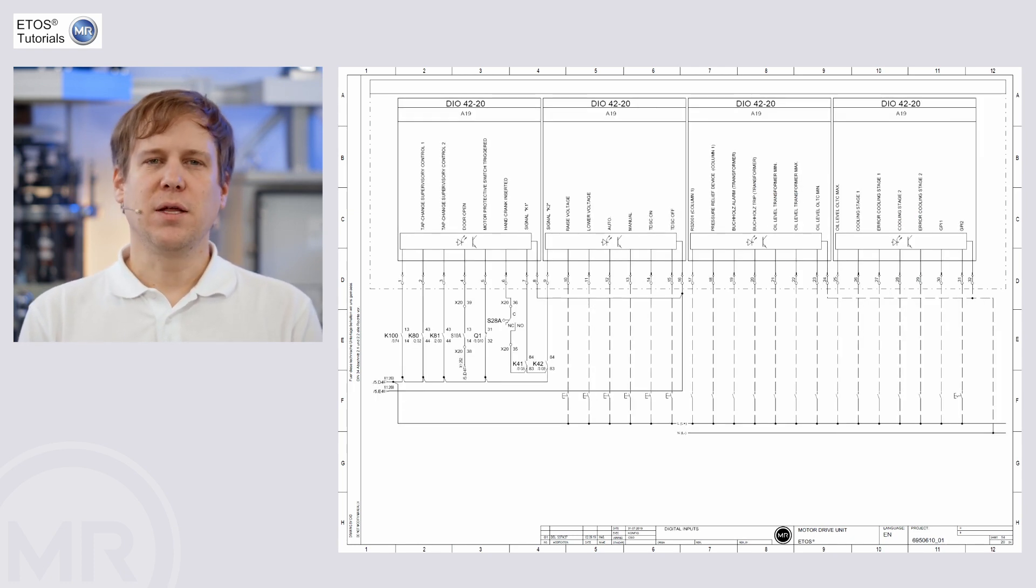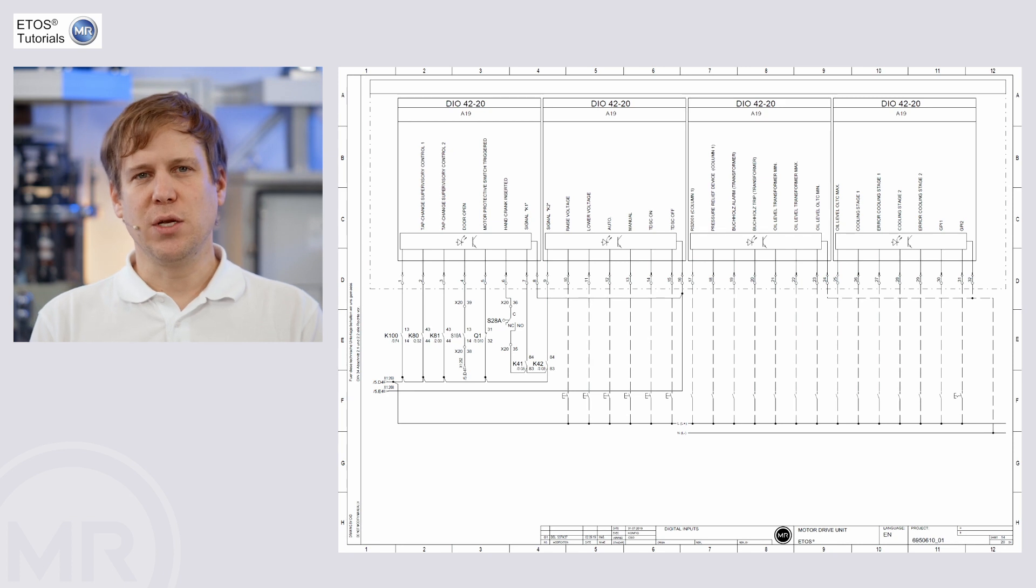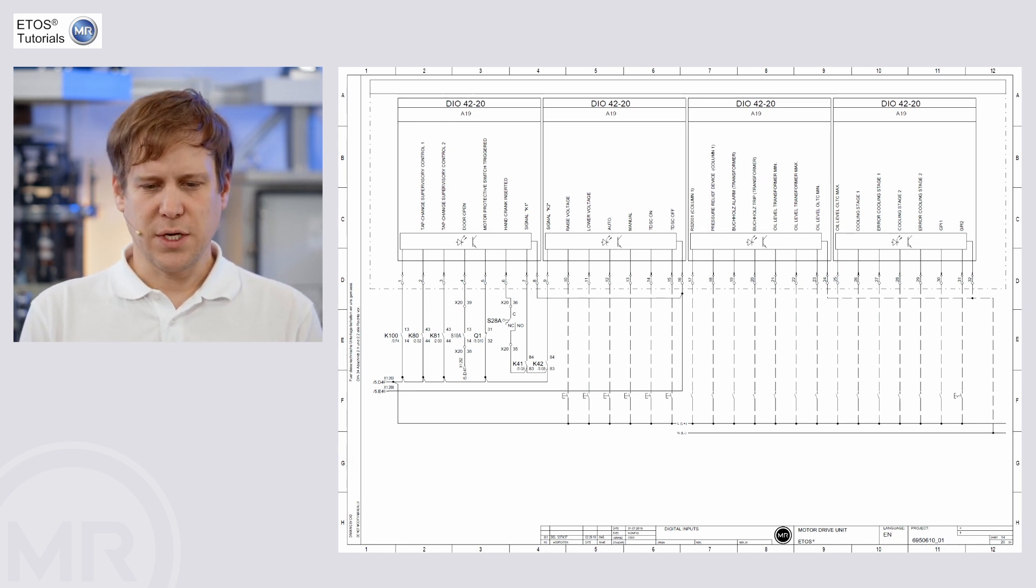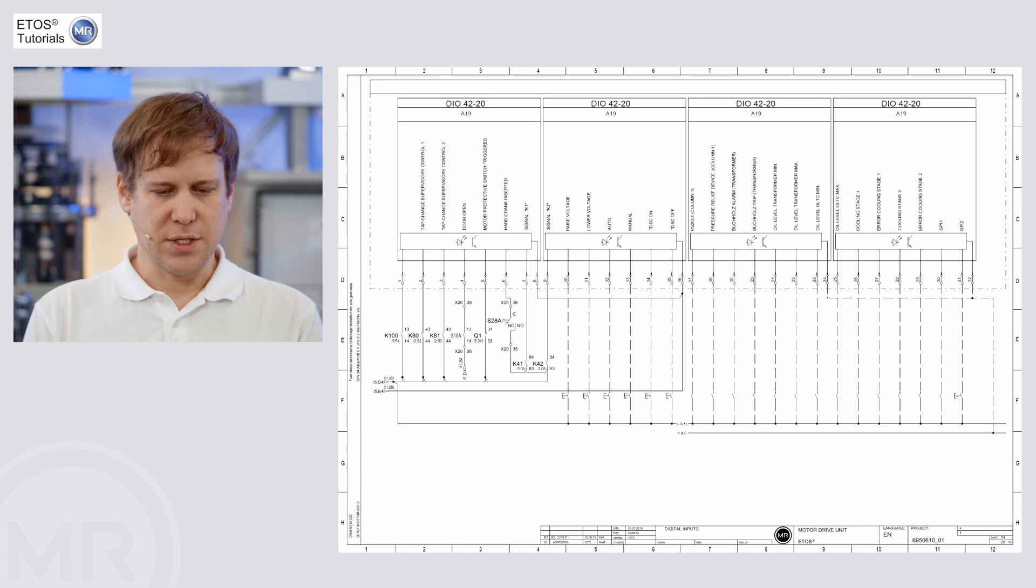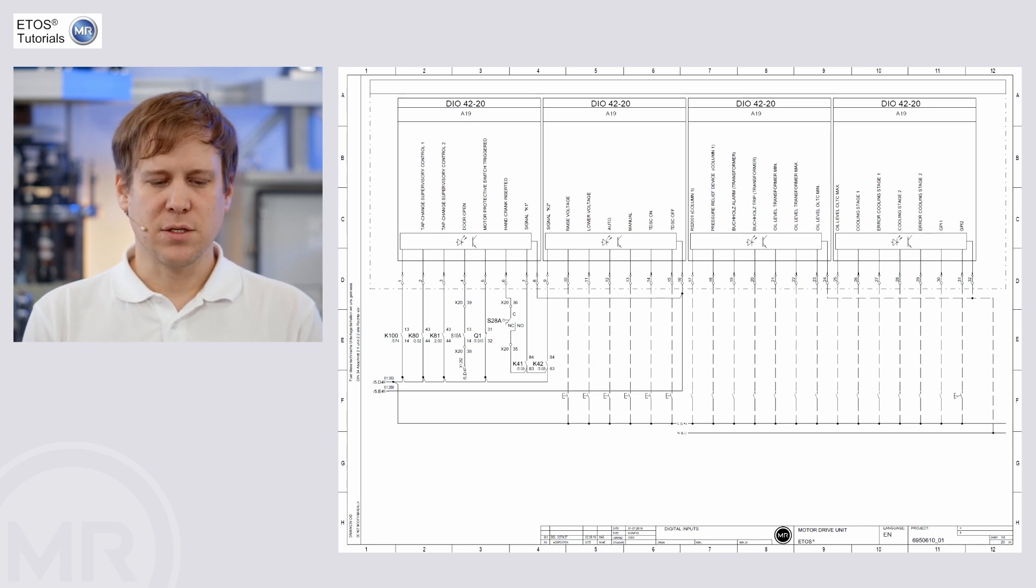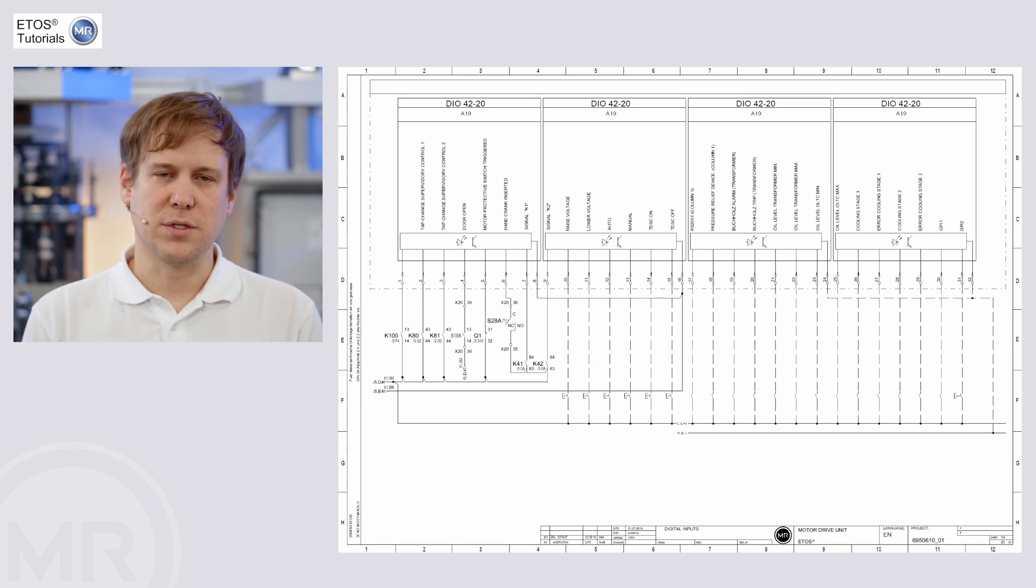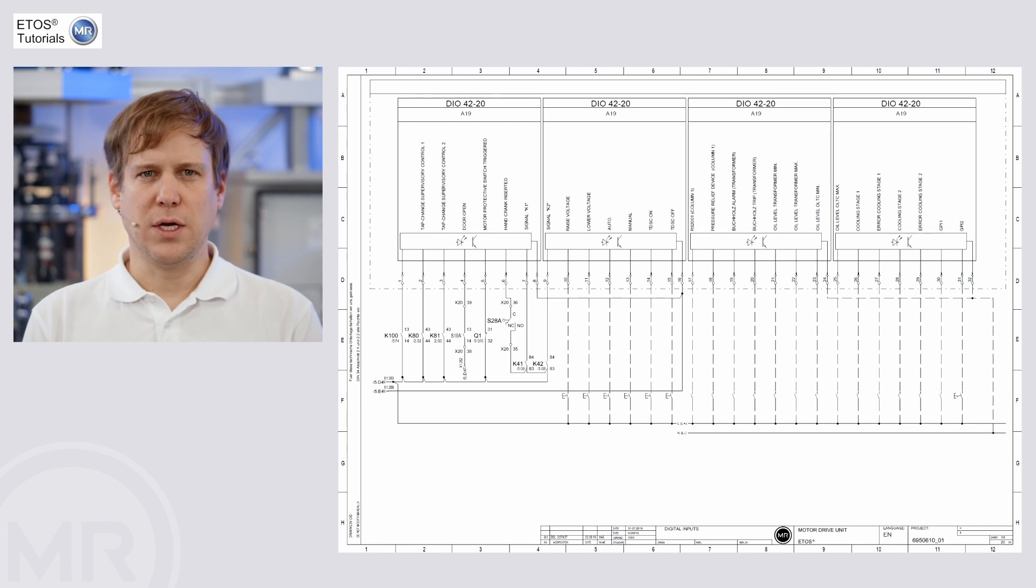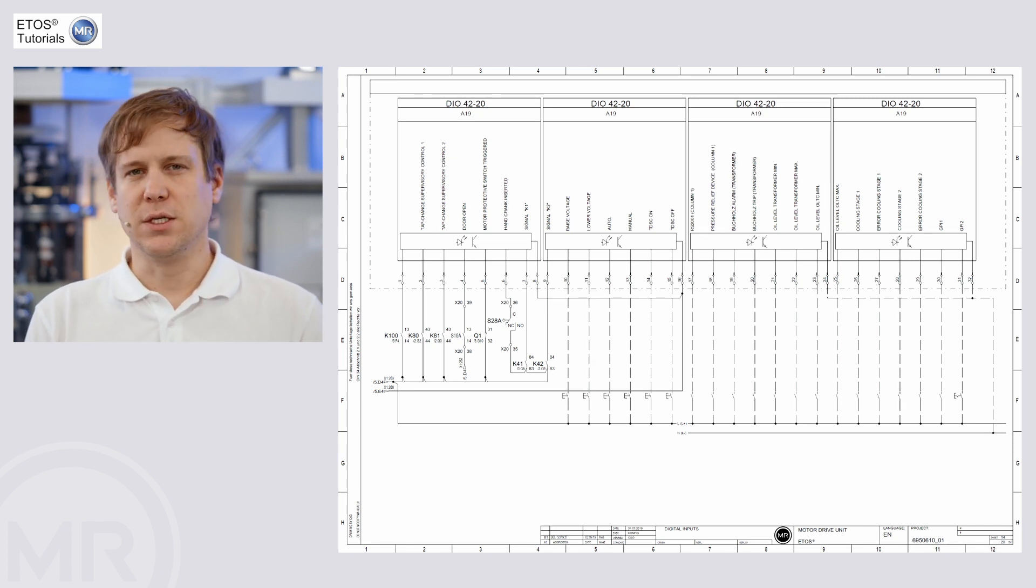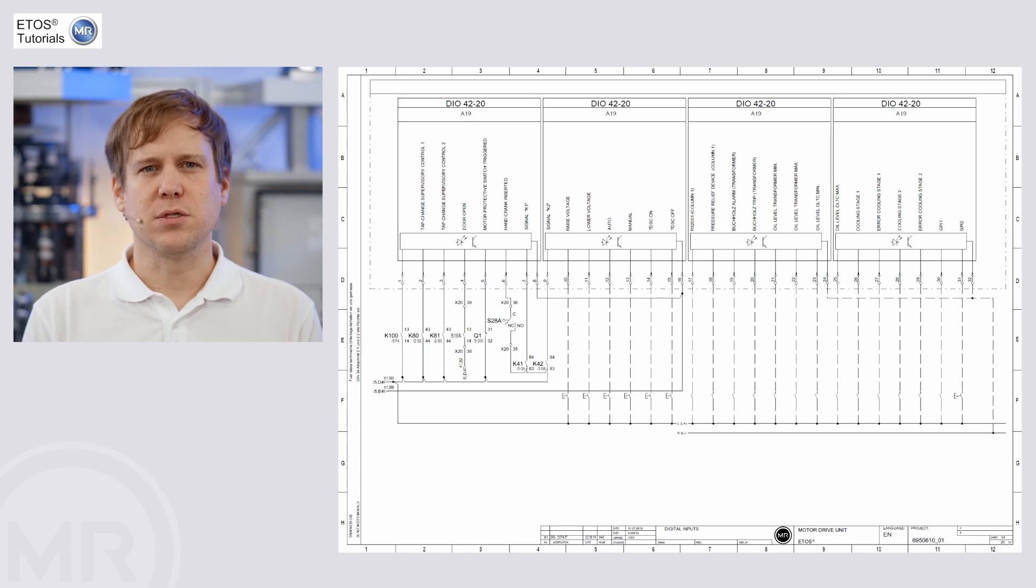Then we can look at the digital input and output contacts. In this case, digital input contacts, for example, breaker contacts, relays and other control signals locally in the cabinet or remote signals from a customer control cabinet or control system.